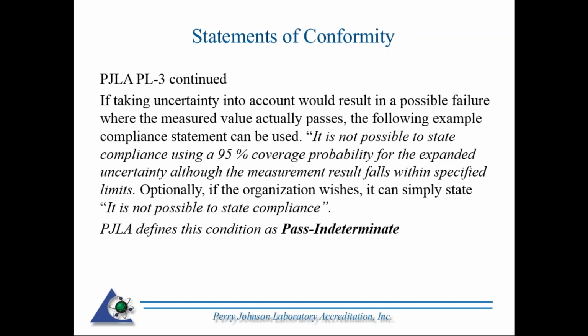So these are those cases where the value is very close to the tolerance limit, however uncertainty may kick it out. We also state in PL3 that we define this condition as pass indeterminate. So an organization, if they wish, can refer to these particular points as pass indeterminate.